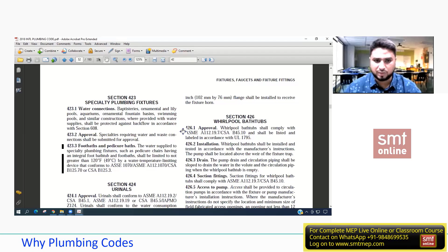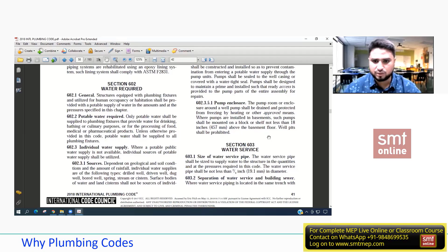That size is also predefined directly from the codes. I'm using the IPC, table number 5037. If you see online, is this table visible? Table number 604.3. This is the water distribution system design criteria, required capacities for fixture supply pipe outlets.